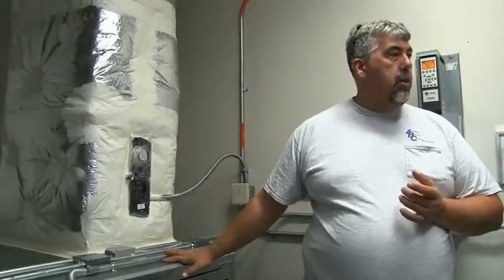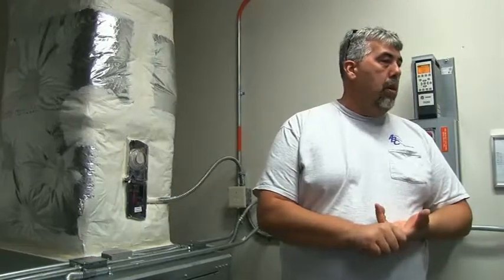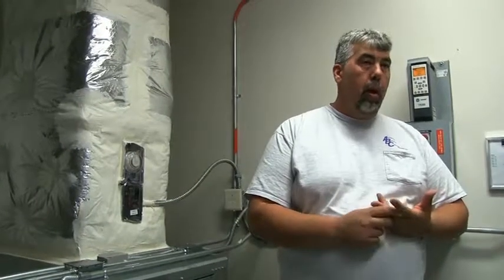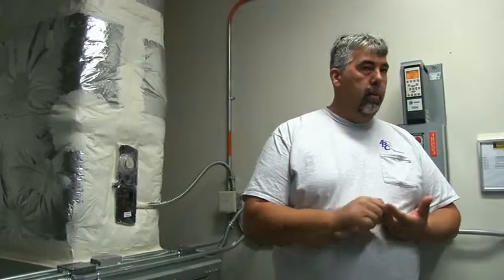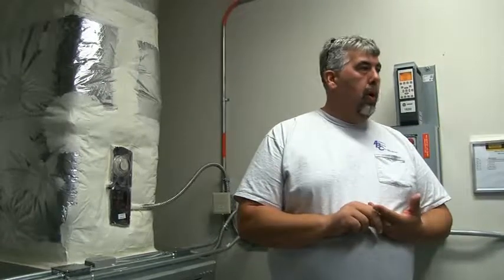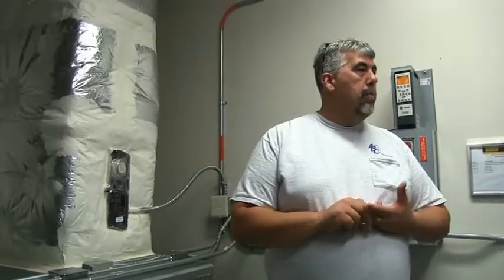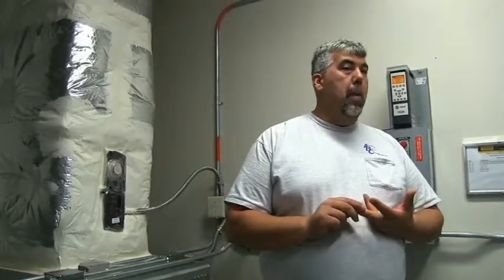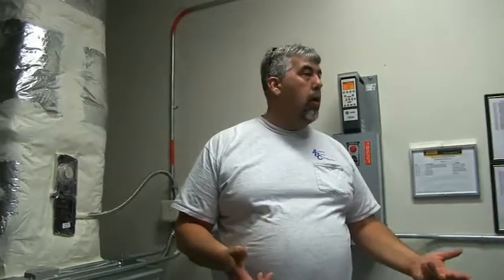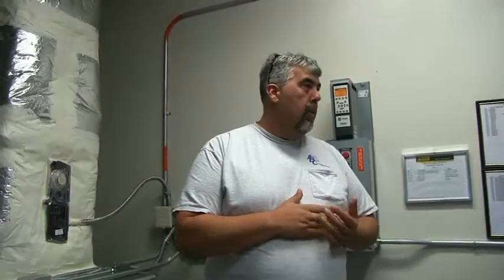So it does do a static pressure reset. It does a temperature reset based on the boxes out there, max cooling call, not temperature. So remember that. Don't go, well, the temperature's 78 degrees, why isn't it resetting down? It's because the set point may be 78 degrees. You know what I mean? So we have to do it off of cooling required for the boxes. And then the static pressure based off of box position.